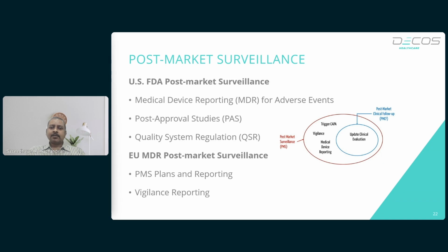For Class 3 devices, such as implantable devices, the FDA often requires post-approval studies to monitor long-term safety and effectiveness. Post-approval studies are conducted based on FDA guidelines to ensure data integrity and provide robust evidence on the device's real-world performance. Manufacturers must maintain an ongoing quality management system to monitor and update device performance throughout the product lifecycle. If issues arise, manufacturers must implement corrective and preventive actions (CAPA) to resolve the issue and prevent it from recurring.